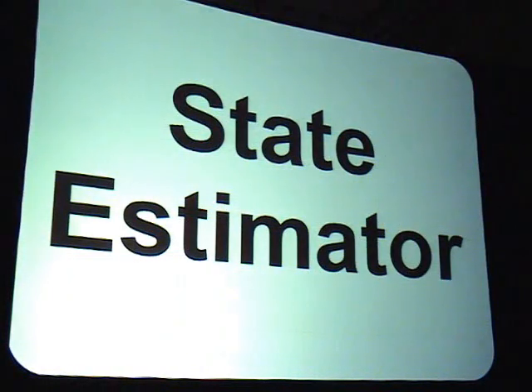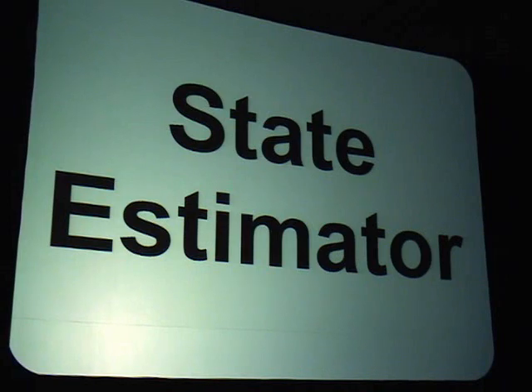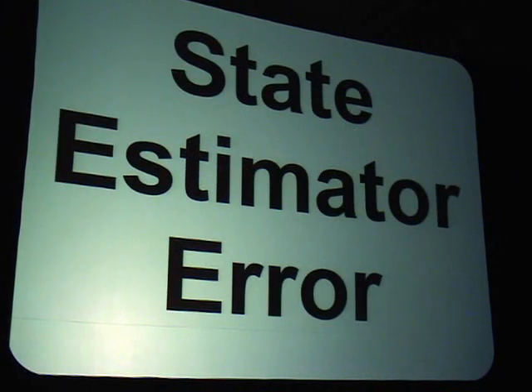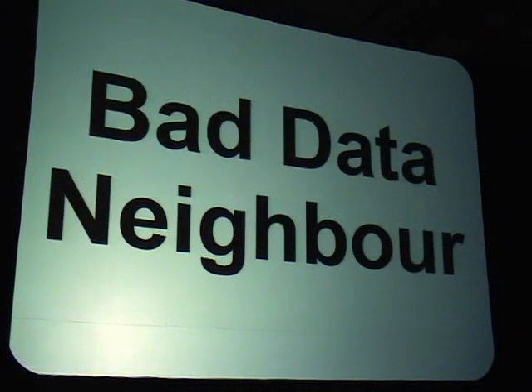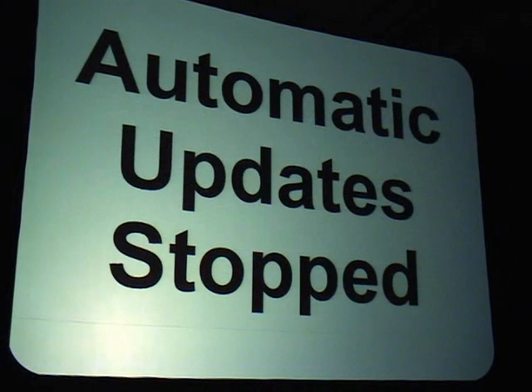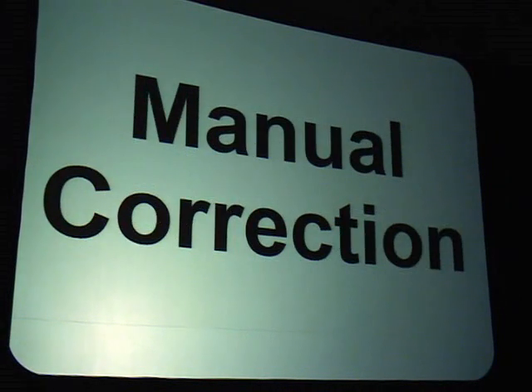Now, they have a piece of software called the State Estimator. What the State Estimator does is it comes up with contingency plans. It runs every 5 minutes and says, here's where we are, here's the worst possible situation, here's what we need to do to avoid that. Much earlier on the day, at 2:15, they started to receive an error from their State Estimator. And the reason they were getting this was from bad data from the neighbour. Now, their software couldn't properly account for this, so they had to stop the automatic updates and go through a manual correction, which took about 45 minutes.